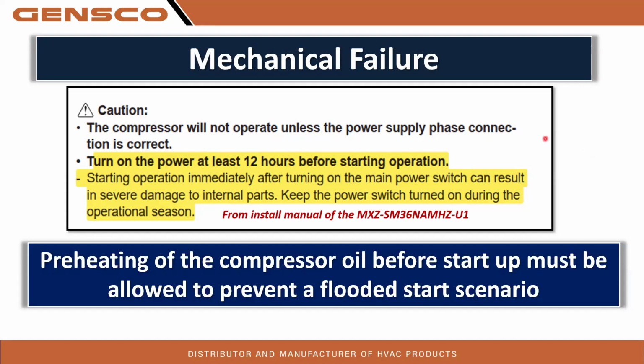So the first start is the most important. Most compressor failures can be traced to that very first start and damage that occurred on it. It's called a flooded start.